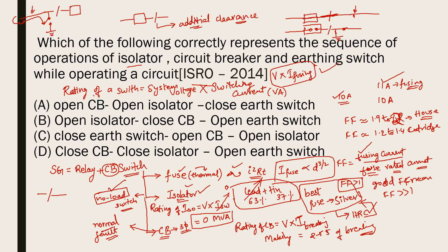Looking at the sequence: Option A says first open CB — when CB is opened, current in the system becomes zero. With zero current you can safely open the isolator. After opening the isolator, close the earth switch, which discharges whatever stored charge remains. So Option A represents the correct sequence: open CB → open isolator → close earth switch.